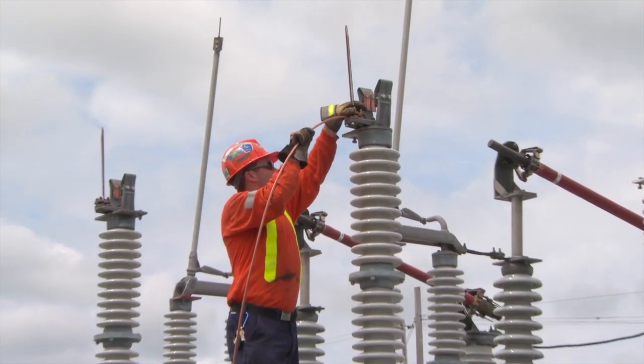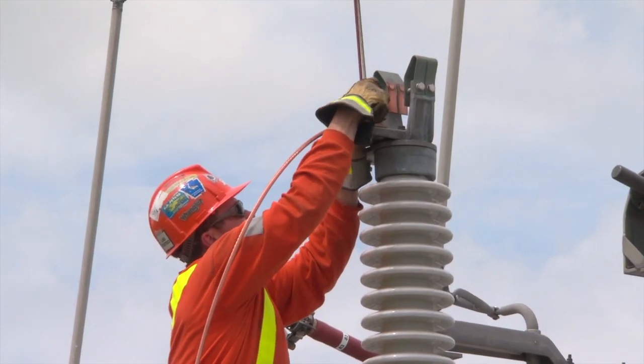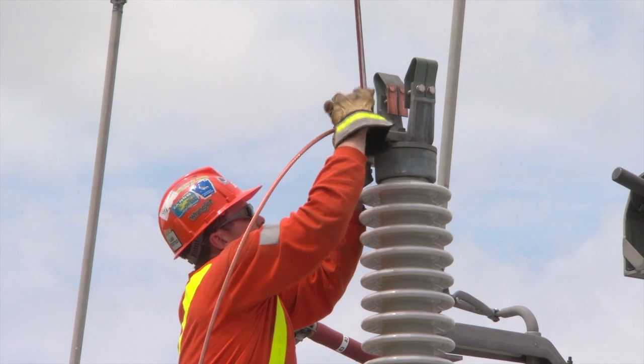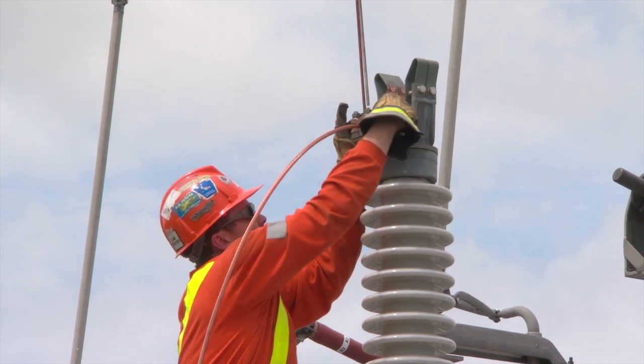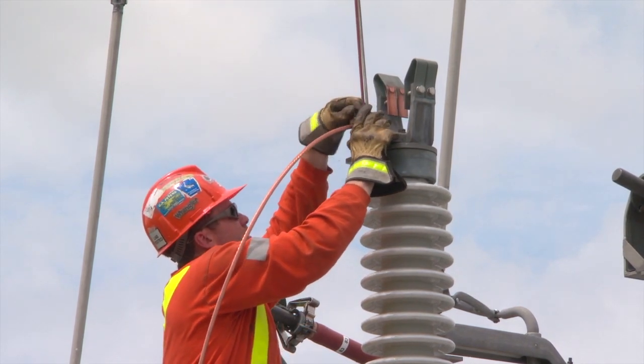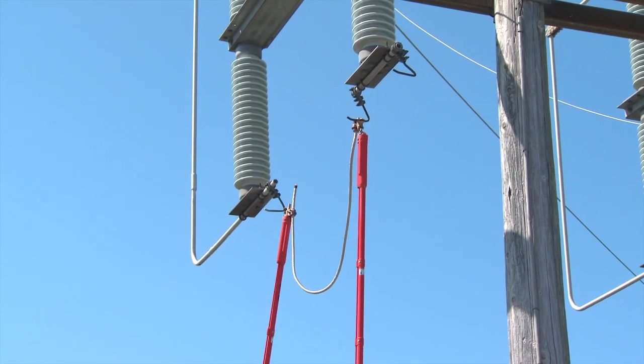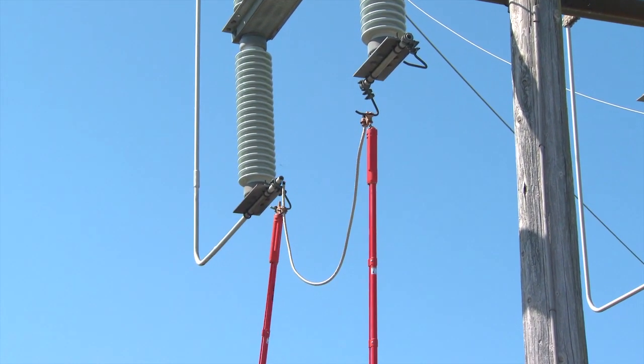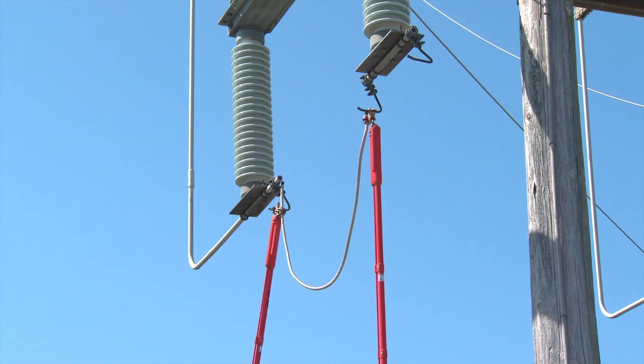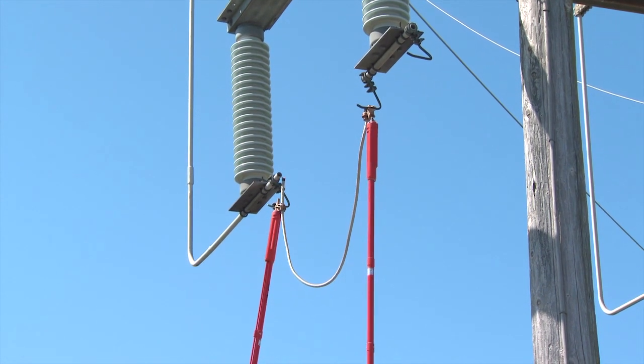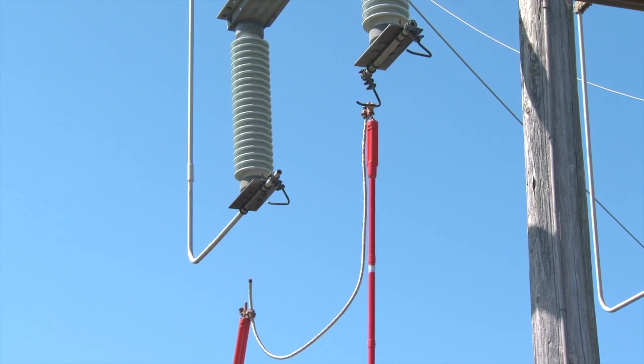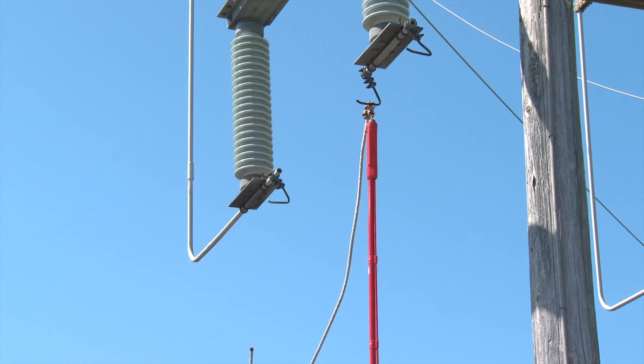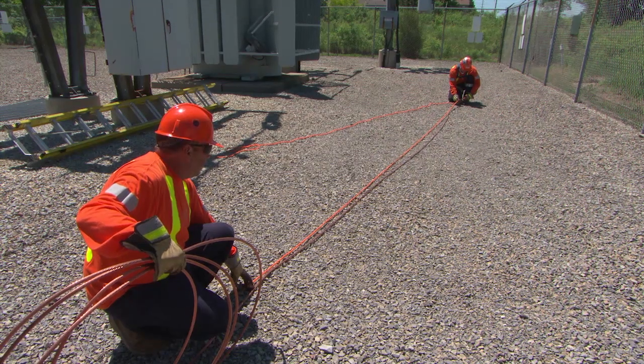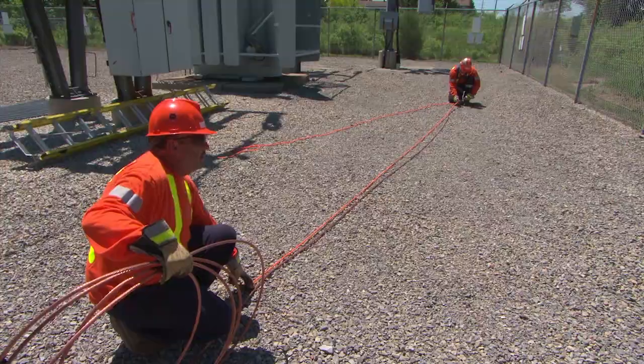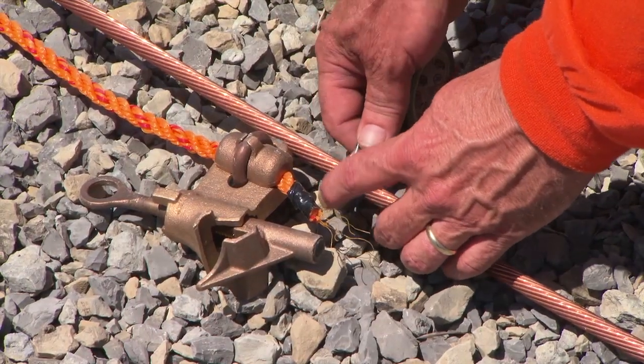Use number 2 bare copper conductor for your high-voltage leads. Measure the required length and cut the conductor to size. A common practice for determining conductor length is to use 3/8" rope and 2 switch sticks to measure the distance between the connection points. When cutting the conductor to size, allow a little extra length for final adjustments. They should be long enough to prevent strain on the insulators, but short enough to maintain electrical clearances.